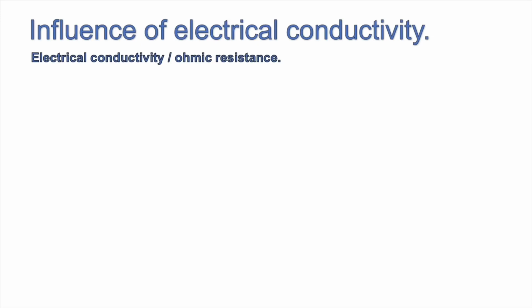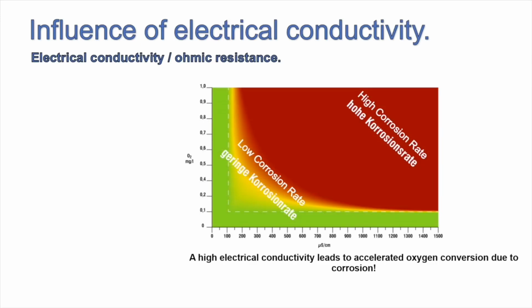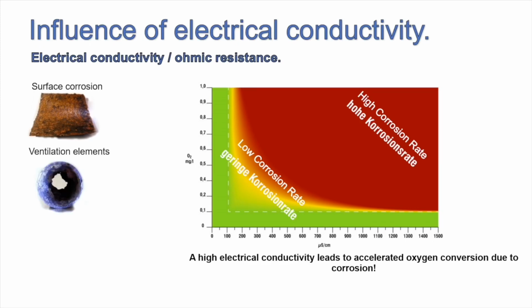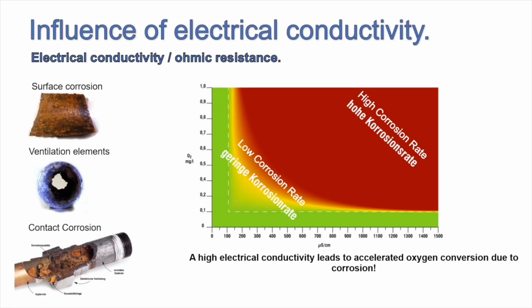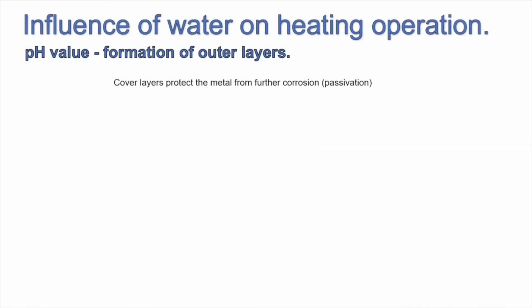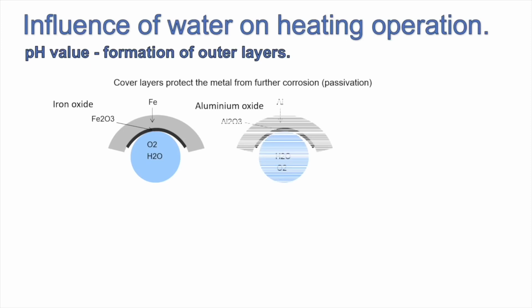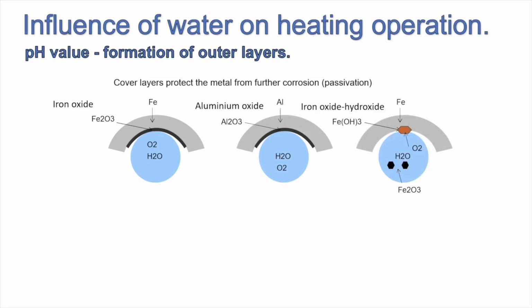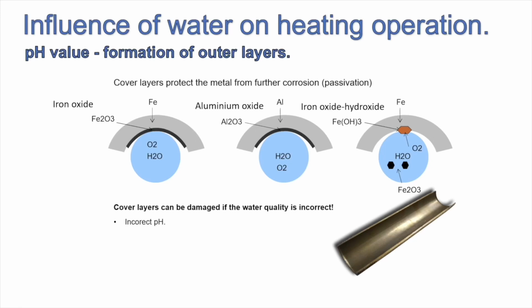Influence of electrical conductivity: this graph indicates the range of the amount of oxygen that we can withstand within our system. The lower the conductivity, the more oxygen we can withstand within our systems, and essentially we can stop corrosion happening at the surfaces of the metals. Looking at the pH value, having the correct pH value allows the metals within the system to become passive. When they become passive, they create their own oxide level at the surface. This surface layer protects against corrosion, even in the presence of oxygen.